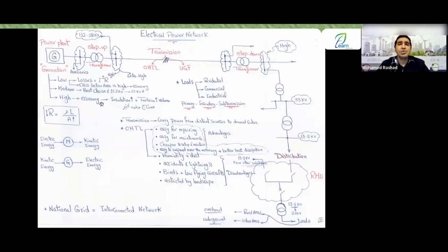My best solution, or best choice, was to generate within the range of medium voltage, starting from 13.8 kilovolts up to 22 kilovolts. So what did I gain from medium voltage? Medium voltage stands in the middle. First, it is not as high as in the case of using low voltage, nor is it very low as in the case of using high voltage. This means I took advantage of being in the middle, where the current is somewhat moderate. My insulation is neither very low like low voltage, nor does it require very heavy insulation like in the case of high voltage. Therefore, the voltage will be moderate and the current will also be moderate.